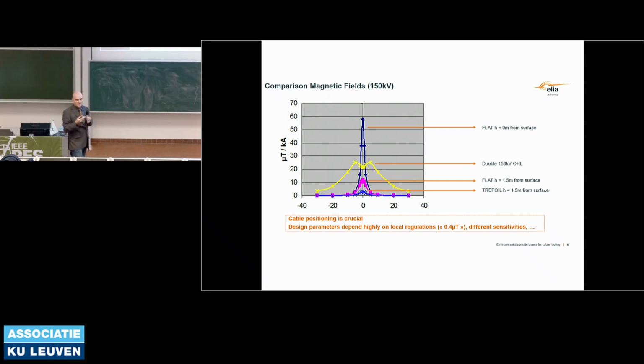So this dramatically gives you options or hampers you in this design. With the double overhead line, you stay somewhere about 4, 5, even 6 times higher than the overhead line. Of course, what you measure there is the field coming off the lowest phase conductors.